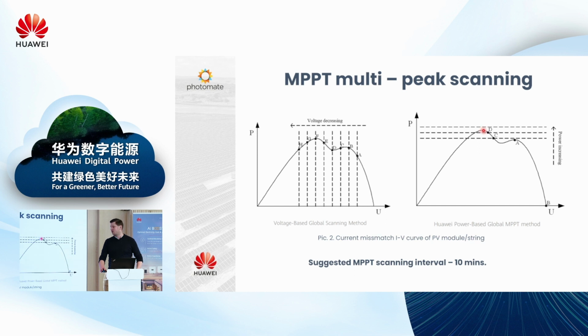That's why you should use this MPPT multi-peak scanning function with the time interval suggested at 10 minutes. So every 10 minutes, the inverter will try to jump out from this area and find this point.